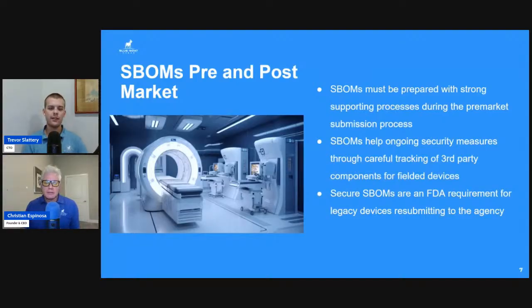What the FDA wants to see, if you have a legacy device that you are resubmitting due to, say, a change in your indication for use or a very minor modification that is not affecting cybersecurity, then you can prepare a reduced burden pathway of that cybersecurity documentation. Part of that is going to be your strategy for post-market management, an assessment of uncontrolled risk in the system, uncontrolled meaning there is a potential for patient harm, and finally, the SBOM, as well as any of that supporting documentation around it, and the safety and security risk assessment of each component in the SBOM.